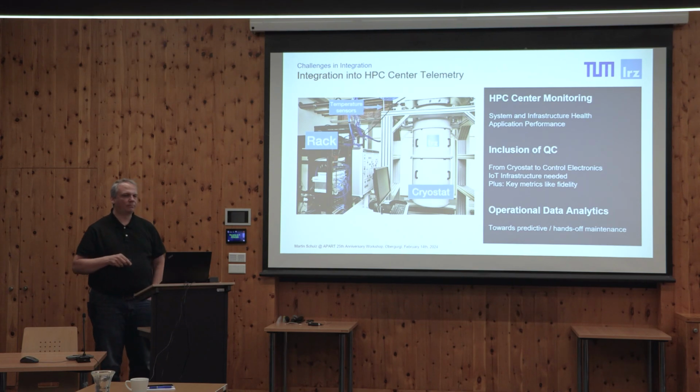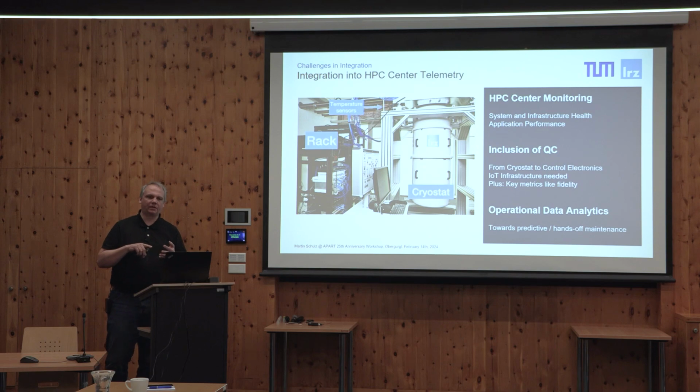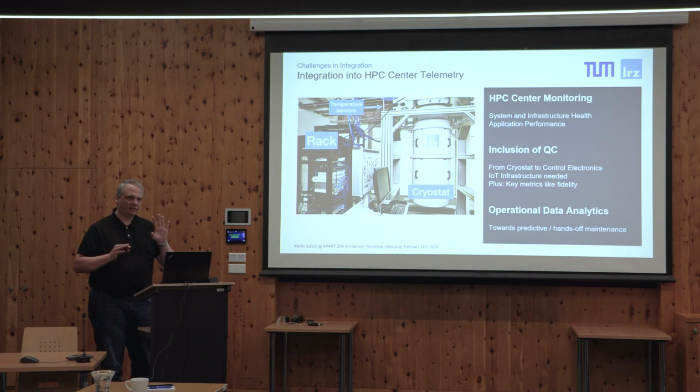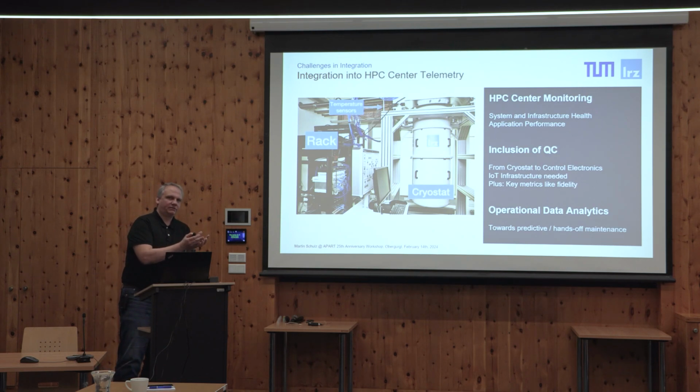Temperature sensors are one part, magnetic waves another thing, vibration, occupancy of the system, power draw of course as well. Temperature, by the way, not just on one line, but we're doing this every 10 centimeters from the ground up to the top of the ceiling. And we're trying to figure out what the changing conditions actually are. And we're piping this straight into a data center monitor, and so hopefully we can then compare it with the error rate that we see.